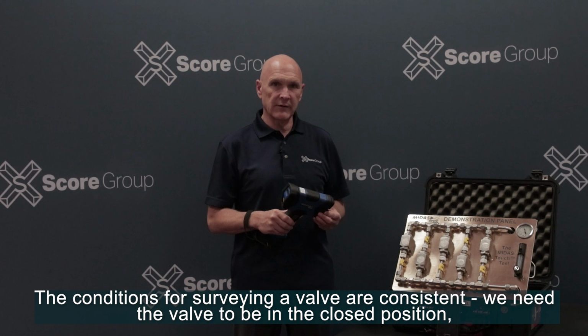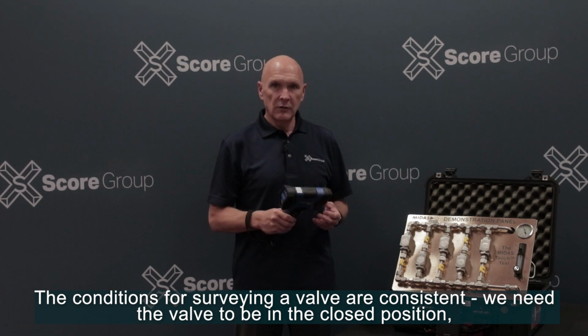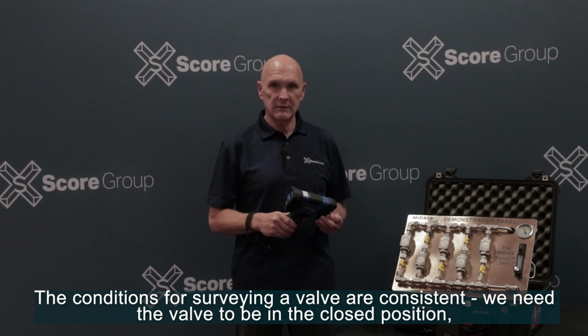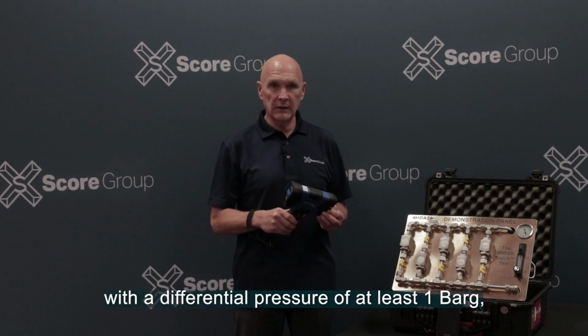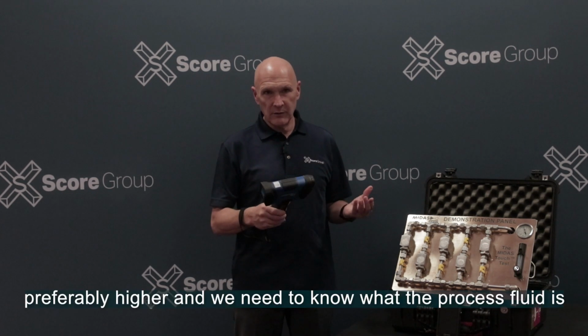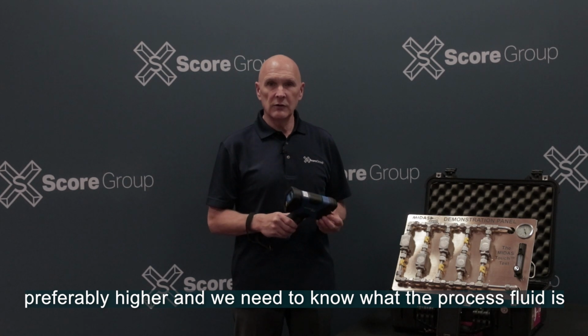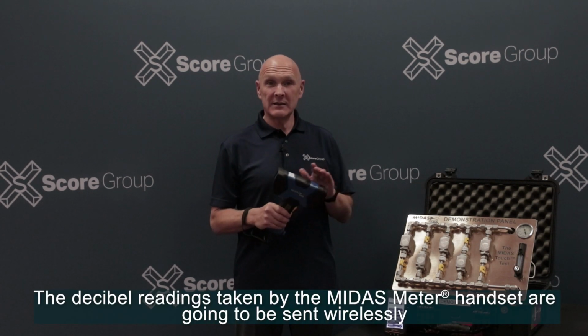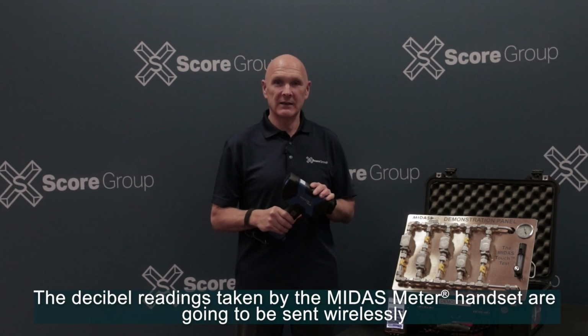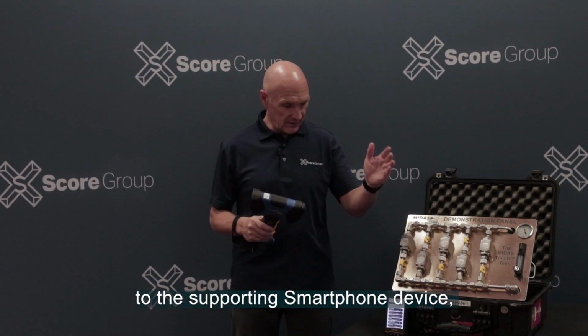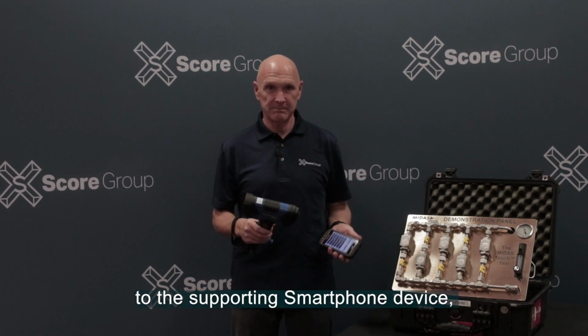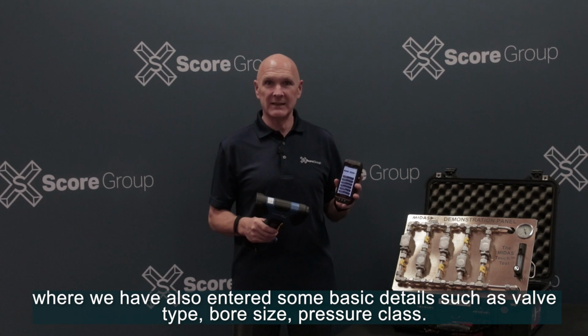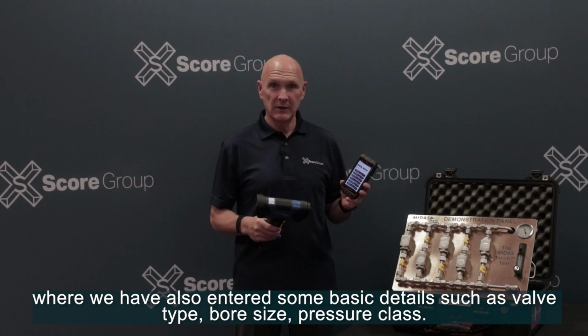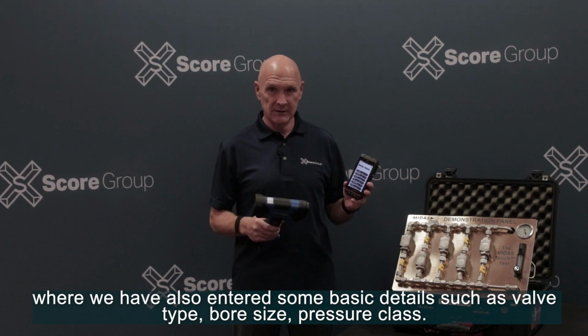The conditions for surveying a valve are consistent. We need the valve to be in the closed position with a differential pressure of at least 1 bar, preferably higher, and we need to know what the process fluid is. For example, liquid or gas or steam. The decibel readings taken by the MIDAS meter handset are going to be sent wirelessly to the supporting smartphone device, where we've also entered some basic details such as valve type, bore size and pressure class.